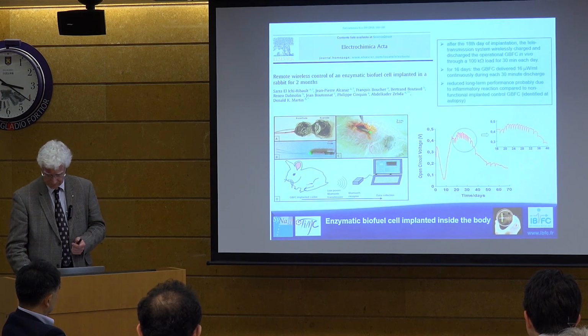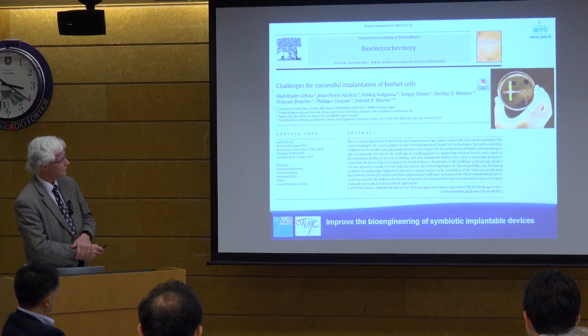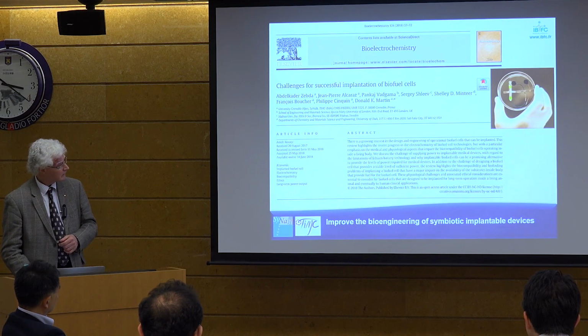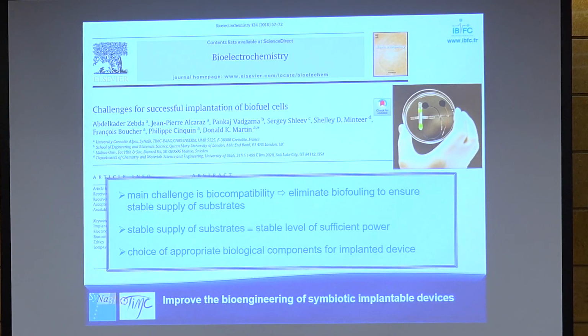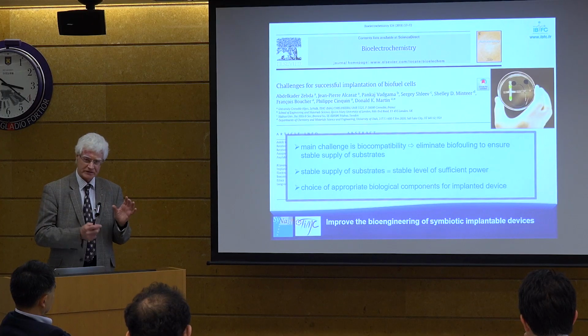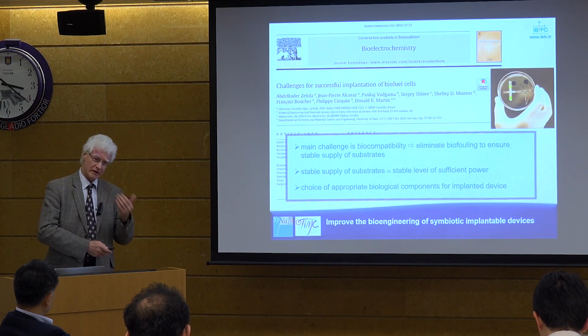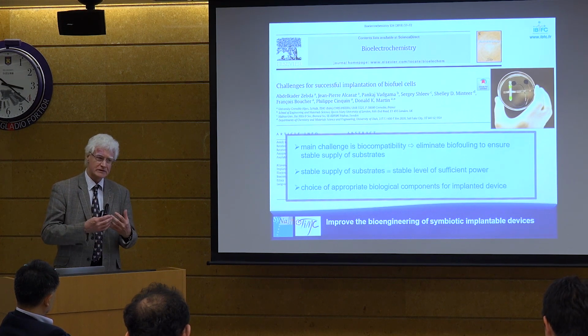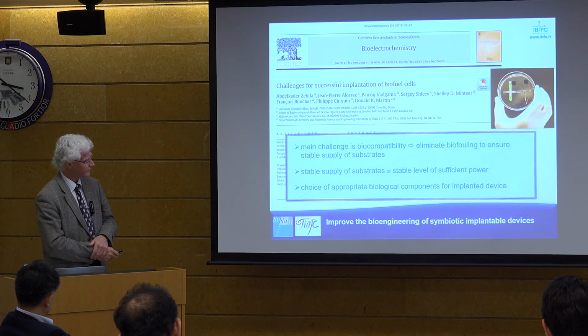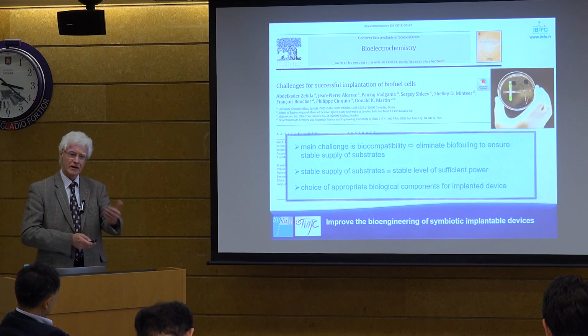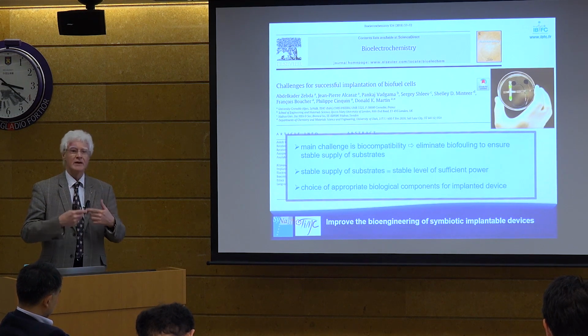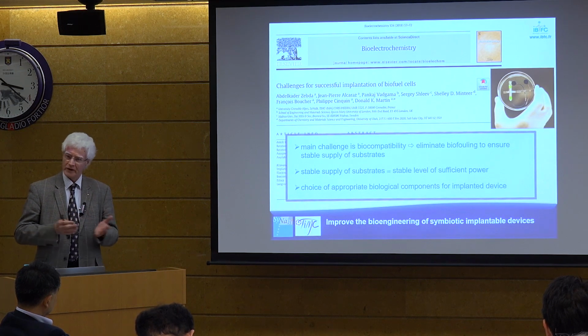So there are still directions to go, which leads us to the challenges for successful implantation, which are biocompatibility, not technical. These are the size of the electrodes at the moment. They can be bigger, they can be smaller. The power output per volume is at the moment 16 microwatts per milliliter, far in excess of what a storage battery can do. Greater power output. But for the long term, the bio-inspired clever nanotechnology really needs to address the issues of biocompatibility. We still have biological problems to solve, which is one of the points I wanted to raise: bioinspired biomimicry is not all about the technology.